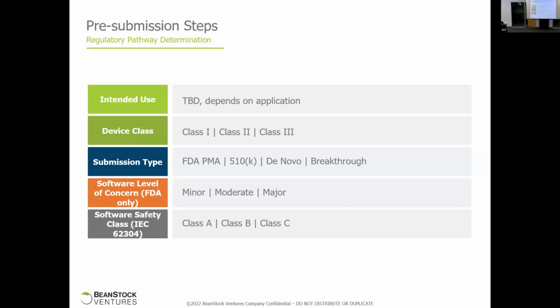And then you have a software level of concern, which has now changed to software documentation level: major and minor, basic and enhanced. And then you have the software safety classification that's recognized by the EU, but also by the FDA, that's followed quite a bit. So it's just a really well-known guidance, or safety standard, related to software.